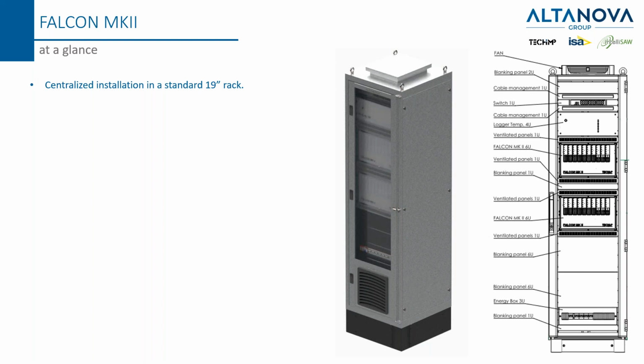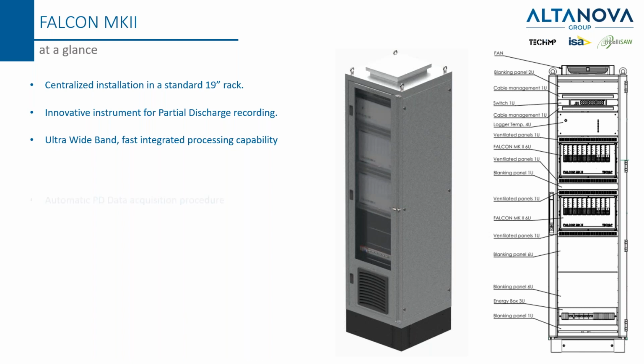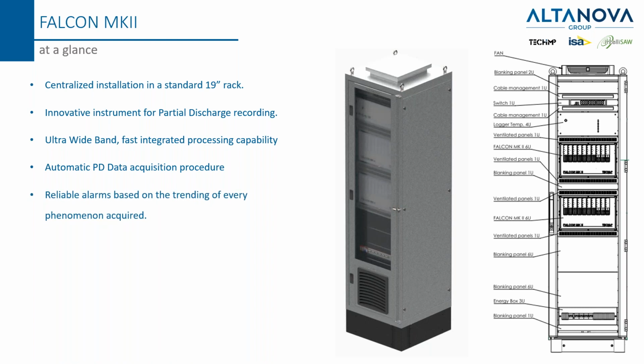Basically, some highlights of the system: the centralized substation installation is inside a standard 19 inches rack. The instrument is innovative for partial discharge recording, with ultra-wideband fast integrated processing capability and an automatic partial discharge data acquisition procedure. So again, the system is totally automatic. It can provide reliable alarms based on the trending of every phenomenon. And as we mentioned at the beginning, it is a comprehensive solution that can integrate other modules and systems.